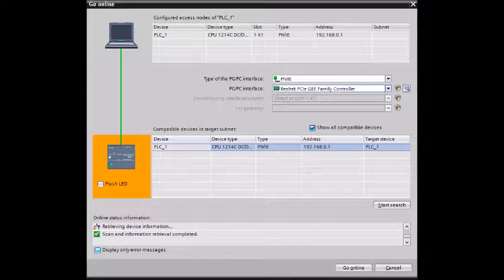One problem I have to mention is connecting the HMI and the PLC to the computer with Ethernet was a real pain in the butt. There was an IP address conflict, which Siemens software somehow did not detect, or it just couldn't connect. It wouldn't tell you what it was. A lot of troubleshooting to realize it was just an IP conflict, which seems like it'd be real simple, but when you don't have any indicators, or it doesn't tell you straight up, it's a little bit more challenging. You kind of got to search around to figure it out.